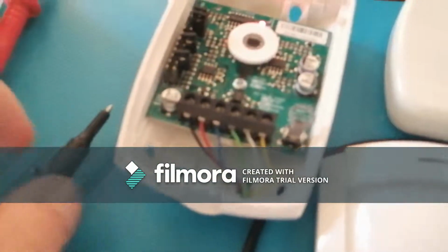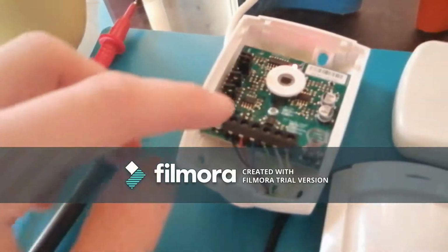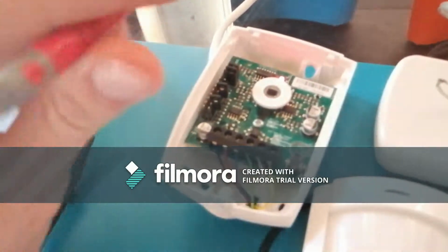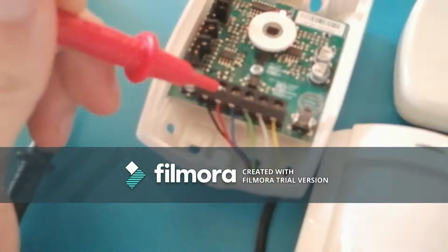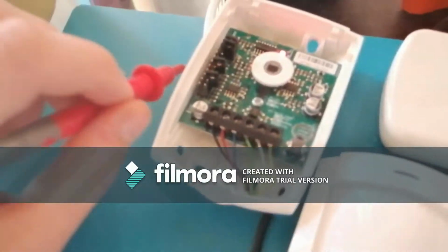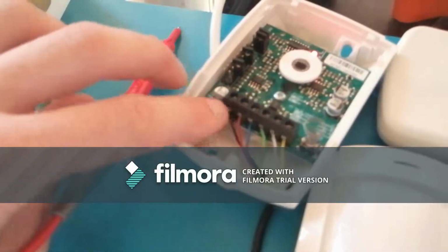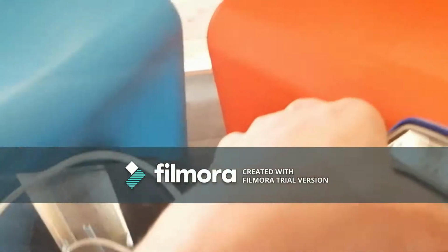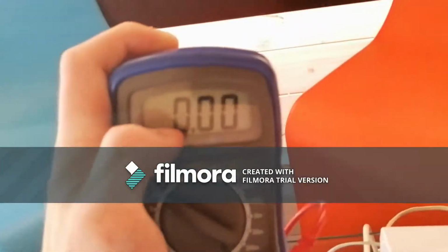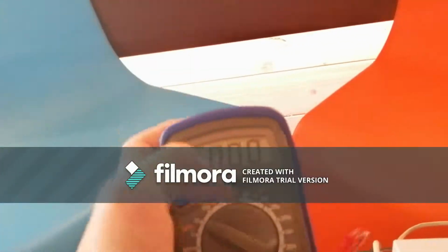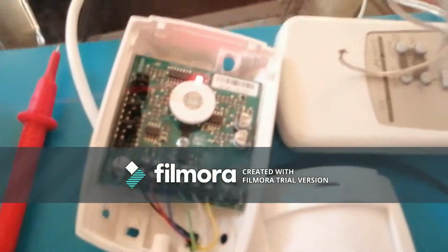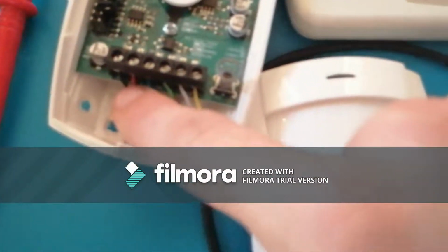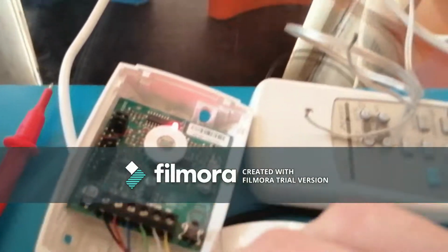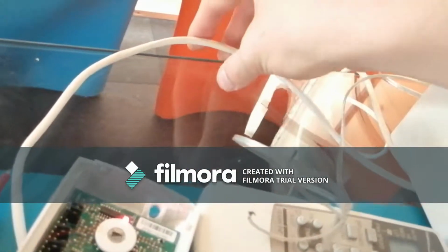So what you want to do is put red to red, so the colours may vary, but positive to positive, so red to red, black to black in this case, on your power input connections. And you want to check that there is 12 or 13 volts present to that detector. If there isn't any power to this detector, then that indicates that there's a cable fault.